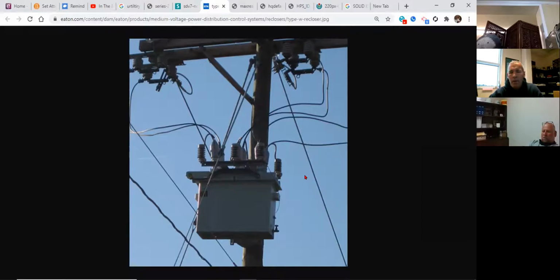If I have a tree limb fall on this line and it falls away, do I want this to reclose? It fell on it, then it fell away, do I want this to reclose and get my power back on? Yes, absolutely. The fault cleared itself on its own, this reclosed, and everybody's happy, they got their power back.